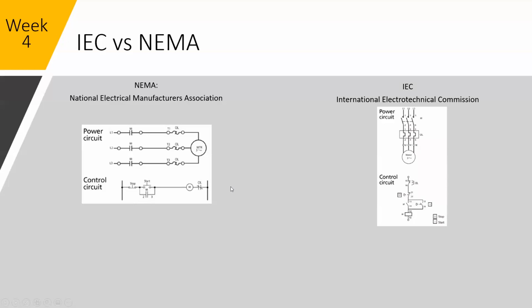IEC is the International Electrotechnical Commission. So again, it's more of an international standard. So if you end up working on Schneider PLCs, Siemens PLCs, panels that are built in other countries, if you start doing work in other countries, the EU, Germany, Asia, you'll see a lot of the international drawings. So you'll notice where the NEMA one is left to right, top to bottom, the IEC standards are top to bottom, left to right. For the most part, they will have some left to right wiring. They'll show parallel circuits to the right, but this is the general layout of the two different standards.